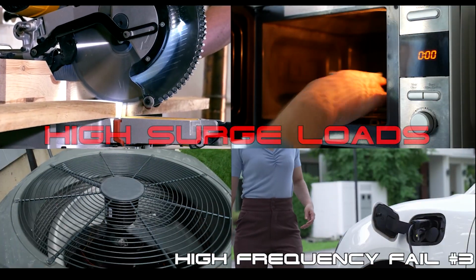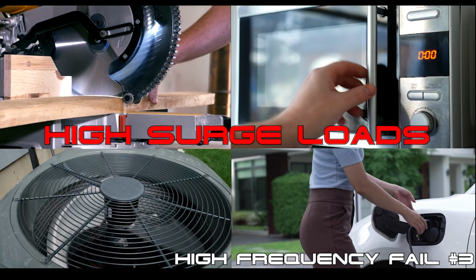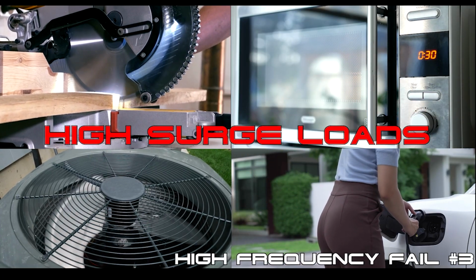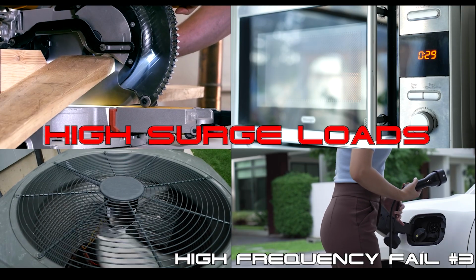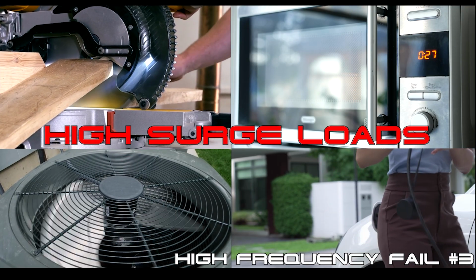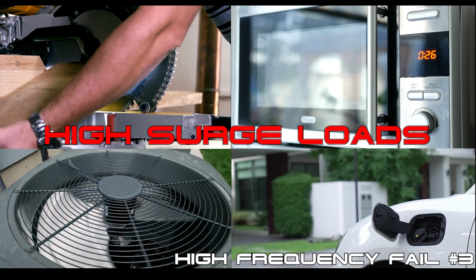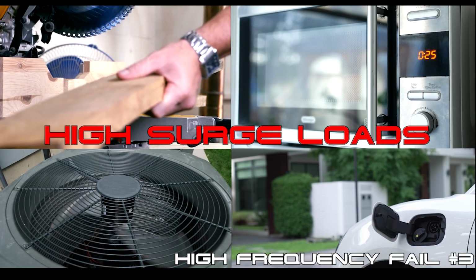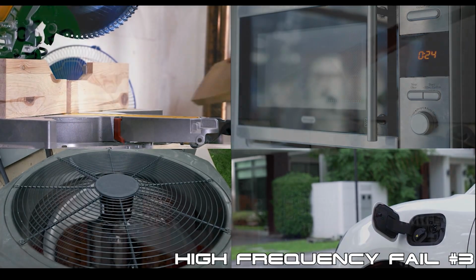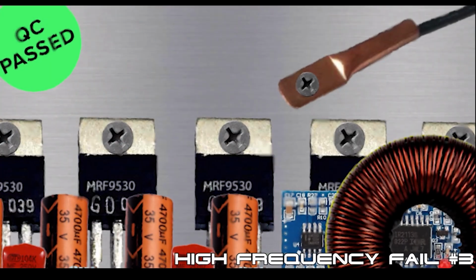High-frequency, transformerless inverters are not designed to repeatedly power high-surge loads such as refrigerators, microwaves, power tools, air conditioning, or EVs. You might be able to power some of these inductive loads when your high-frequency inverter is new, but every time you do, you're shortening the life of the already overstressed MOSFETs and capacitors in your inverter.